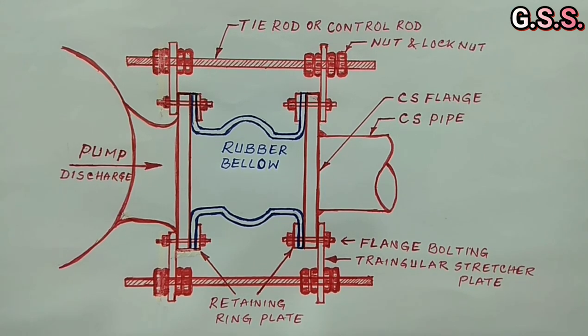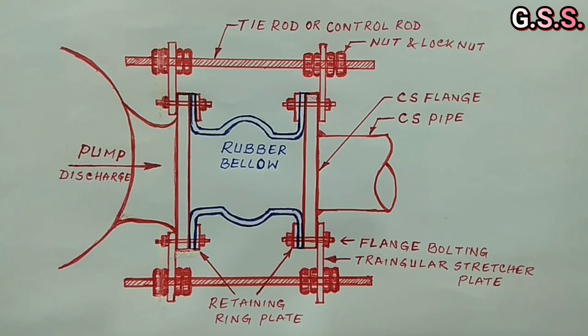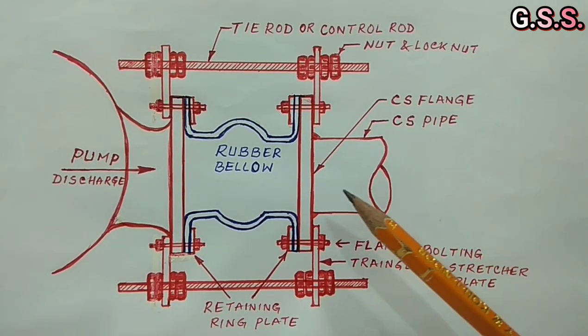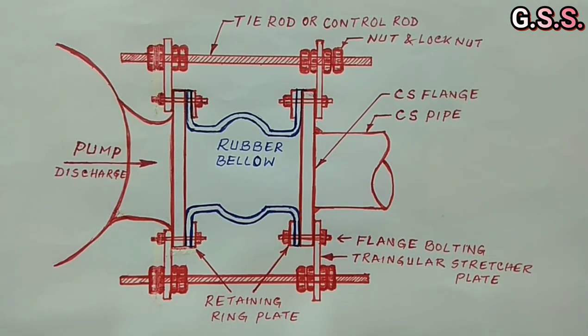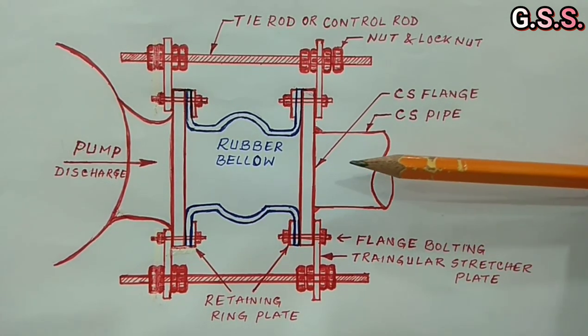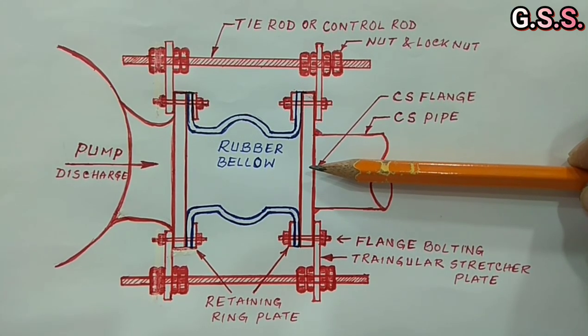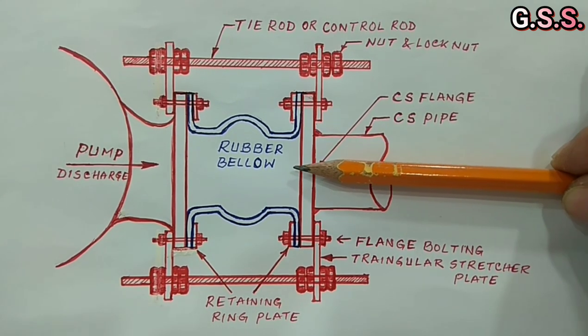Now we will see how the bellow makes the nozzle load free. We can mount steel pipe and flange directly with the pump nozzle. But steel piping alignment cannot be 100% perfect and definitely there will be some minor misalignment in steel piping in axial direction, lateral direction and in angular direction.